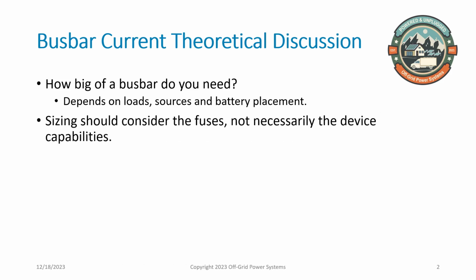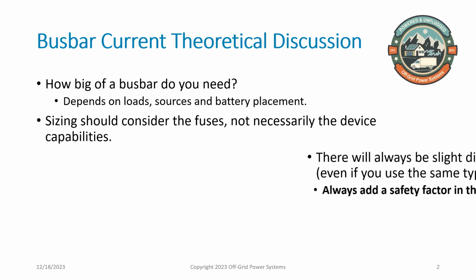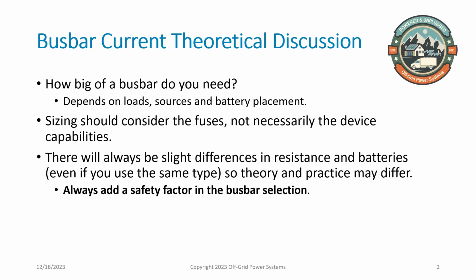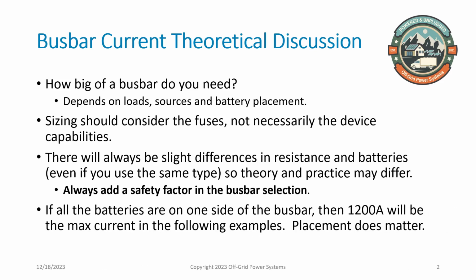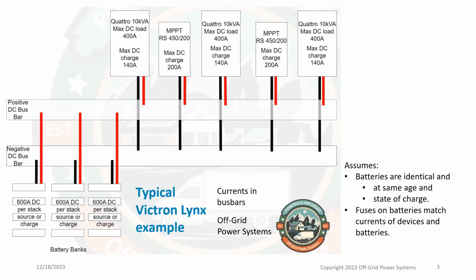this tutorial. Sizing the bus bar, as with wires, should be based on the fuses, not the devices, since the devices could supply or source more current than expected in a failure mode. Since all the components, including wires and connections, will have some variations, a safety factor should be included. We'll show you that placement of the sources and loads does have an impact on the size of the bus bar you need. Rigorous electrical circuit analysis is not given, just the results.